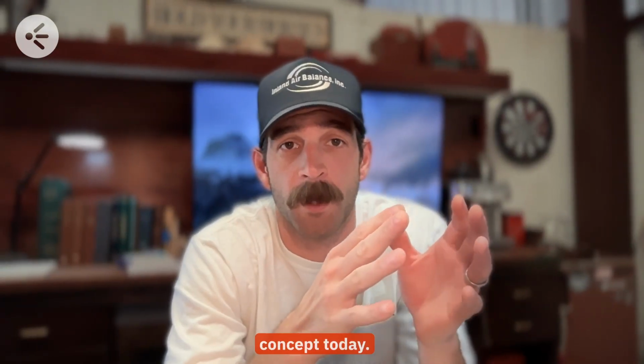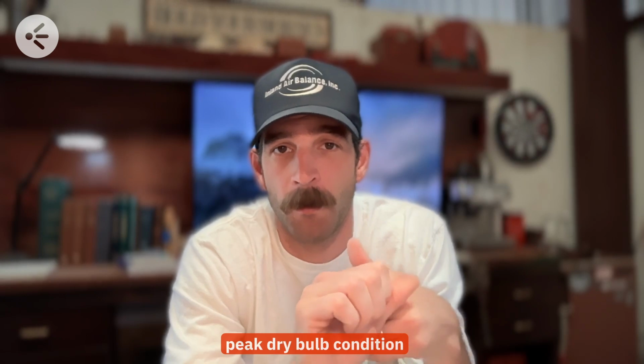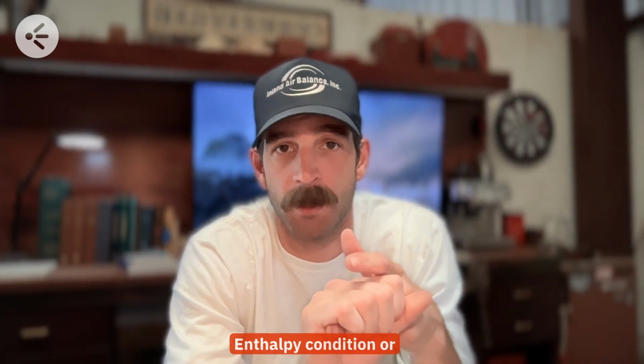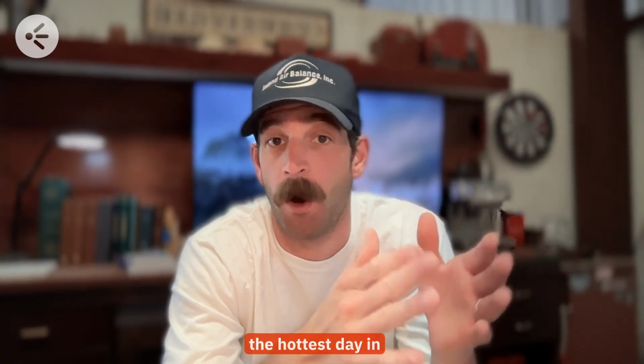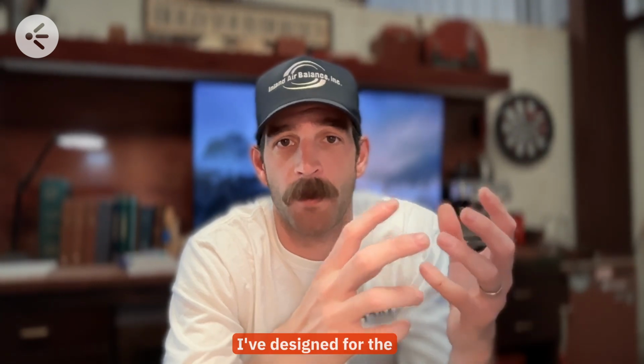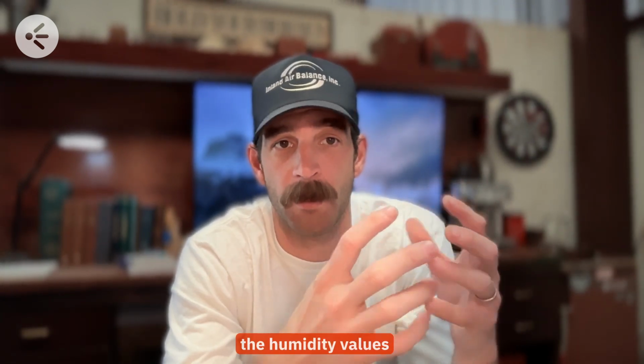Super important concept today. We're talking about summer design conditions. The difference between your summer peak dry bulb condition and your peak enthalpy condition. Or you can think of it as, should I design for the hottest day in the summer, or should I design for the wettest day in the summer and include the humidity values in that assessment?